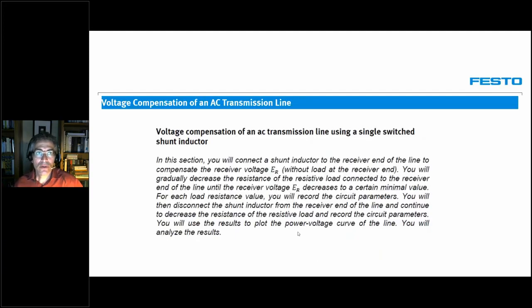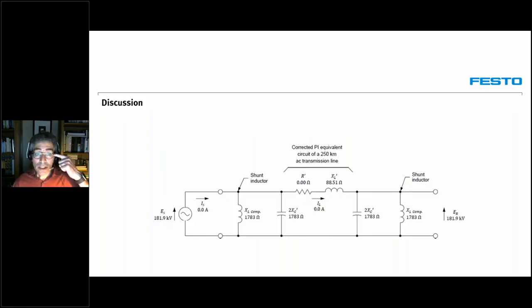So we need to be able to stabilize this voltage at the receiving end, and we will do that through voltage compensation. Voltage compensation is achieved by adding compensating inductors at both ends of the line, which try to compensate for the capacitive nature of the line. We will be able to remove these compensating inductors depending on the load, so depending on the current that is flowing. By adding compensating inductors that have the same value as the equivalent capacitance of our transmission lines, they will cancel out at each end, and then we will only be left with the inductance.